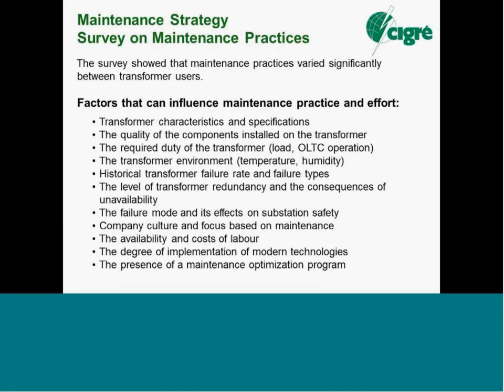Is the transformer appropriately specified for its environment? Its pollution and marine corrosion, typical examples, are going to affect its maintenance effort. Is the way it's loaded, the harmonics it's dealing with, going to prematurely age the transformer? So it's important to understand how it will be operated, where it will be operated, and do we specify maintenance devices for the transformer. That's the second dot point, the quality of the components installed in the transformer. The required duty of the transformer, the environment which we've spoken of, the historical transformer failure rate, and failure types.